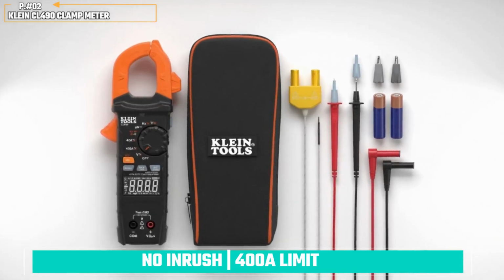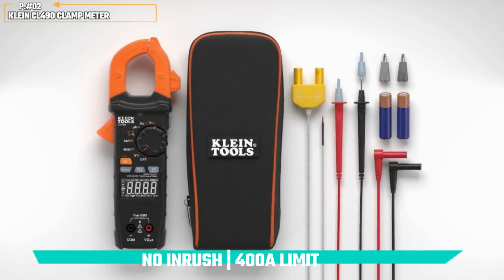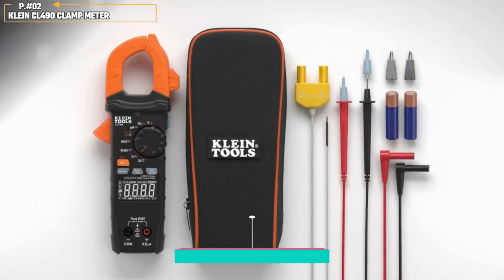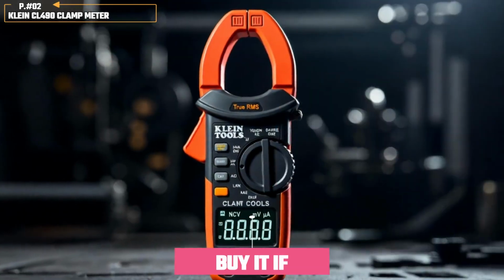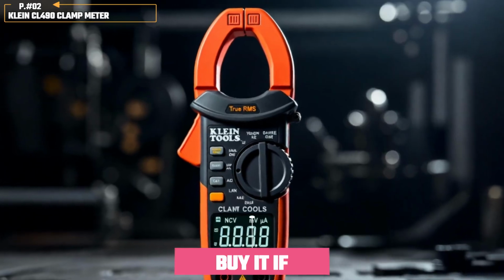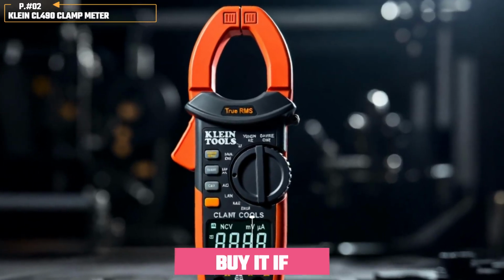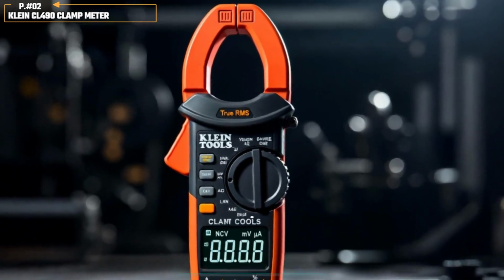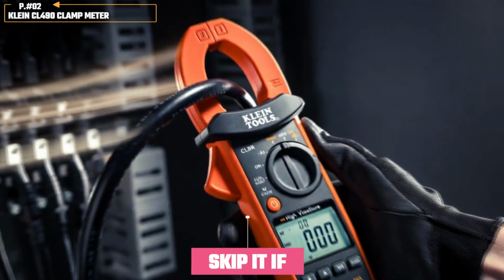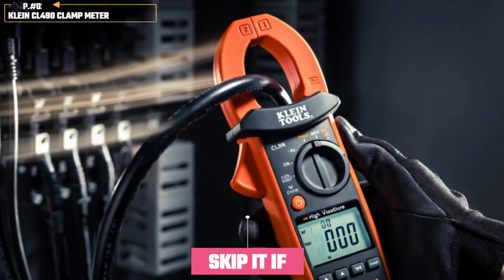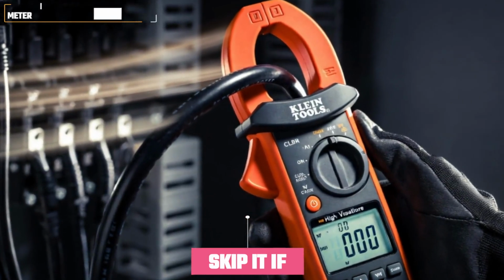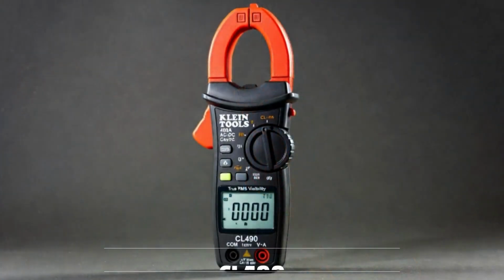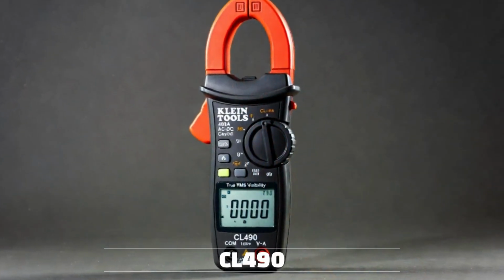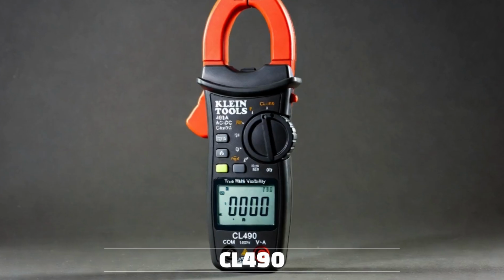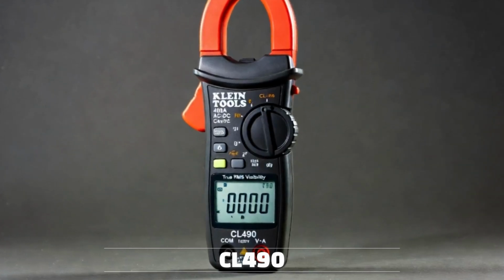It also lacks dedicated inrush capture and data logging, and the magnetic hanger is sold separately. Buy it if you want strong job site visibility, professional safety compliance, DC microamp testing, and practical everyday durability. Skip it if you need higher current measurements, motor startup capture, or long-term recording. The CL490 earns second place for its dual-angle display, dependable measurement range, and field-friendly design.